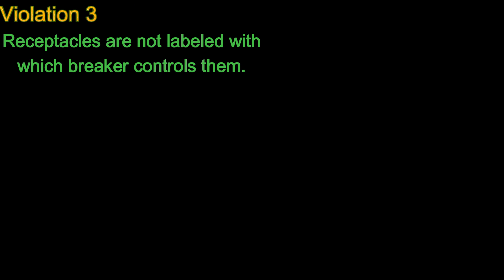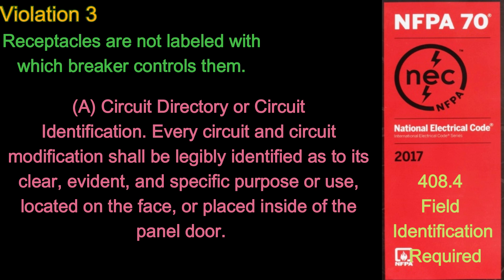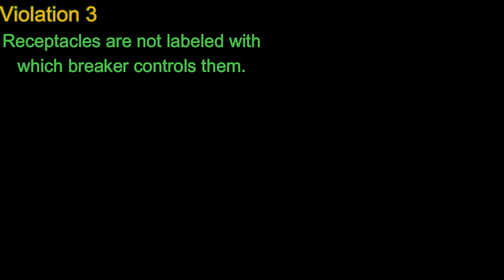Number 3: Receptacles are not labeled with which breaker controls them. Code NFPA 70 408.4, field identification required, states a circuit directory or circuit identification — every circuit and circuit modification shall be legibly identified as to its clear, evident, and specific purpose or use, located on the face or placed inside of the panel door. Solution: Use more permanent labeling and keep it current with changes due to remodeling.